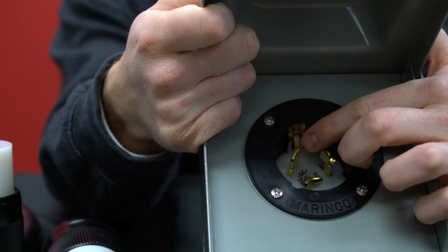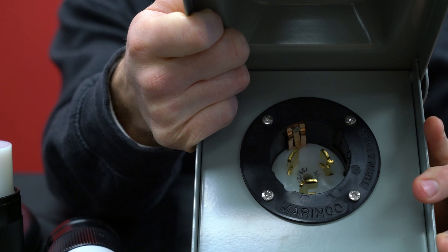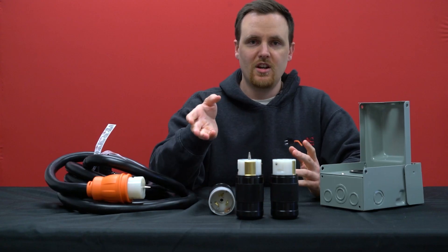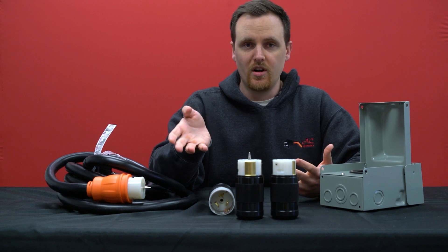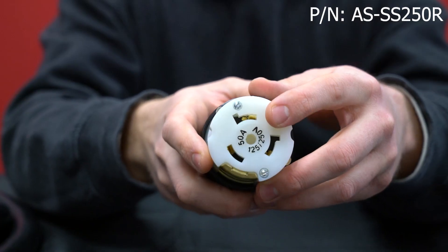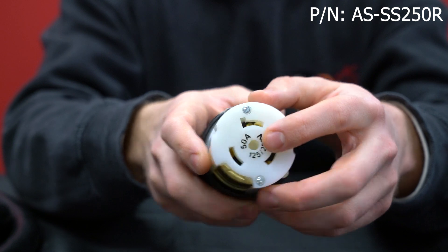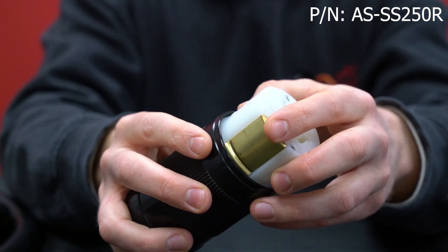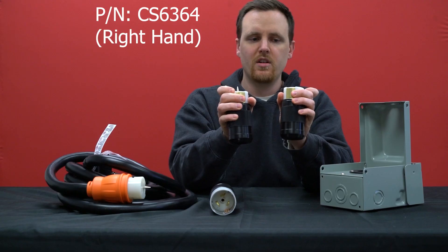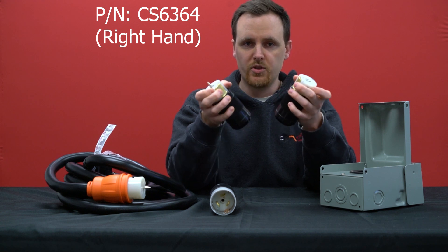The fourth prong is on this wall right here, and it's not just a random piece — it actually acts as the grounding prong, which is important for safety. The same goes for AS-SS250R female connectors and CS6364 female connectors. That bigger copper piece on the wall is the fourth prong, also for grounding.